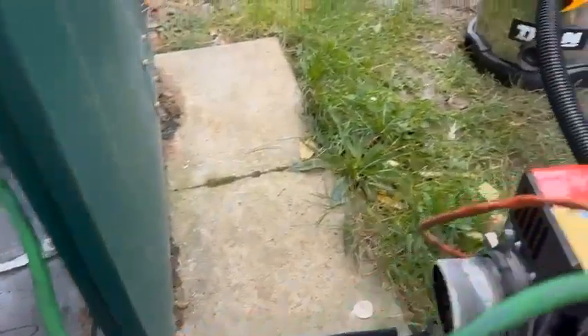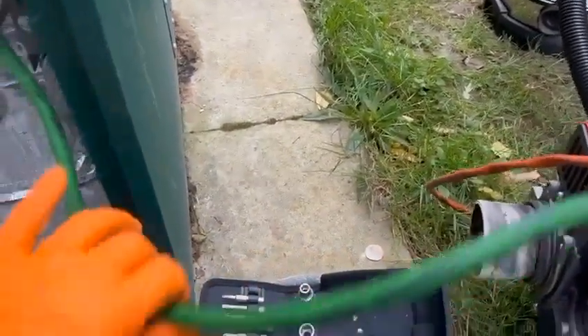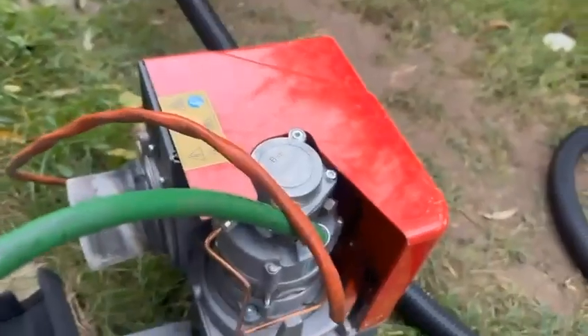It's a flexible oil line. Really flexible still. I've looked at the date on it. It's only 2 years old, so that's absolutely fine. That's still fine. It's a bit dirty, but it's fine. And I'll just give it a sniff, yeah, and that's absolutely fine as well, because sometimes they bend and smell a bit. We're going to go onto the burner now.